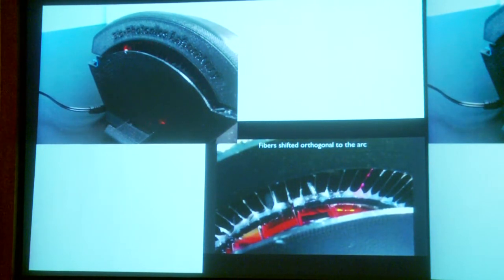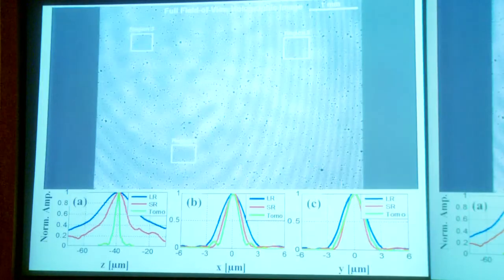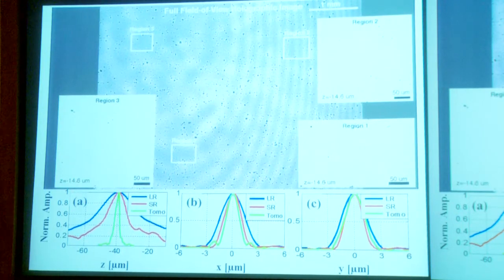The sample is inserted from the side. And if you focus on this movie, all of the light sources are attached to a bridge, and they are being electromagnetically actuated so that we capture a super resolved hologram of one angle and advance to the other one. As a result of that, we can have a field portable microscope that can look at cells in 3 dimensions and slice them up in Z, which again is quite nice, especially considering the fact that it's a quite inexpensive and field portable device.